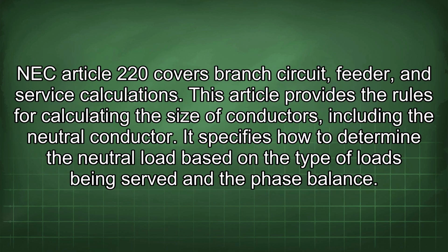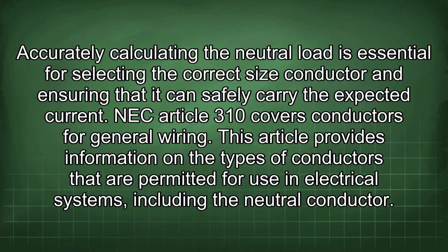NEC Article 220 covers branch circuit, feeder, and service calculations. This article provides the rules for calculating the size of conductors, including the neutral conductor. It specifies how to determine the neutral load based on the type of loads being served and the phase balance. Accurately calculating the neutral load is essential for selecting the correct size conductor and ensuring that it can safely carry the expected current. NEC Article 310 covers conductors for general wiring. This article provides information on the types of conductors that are permitted for use in electrical systems, including the neutral conductor.